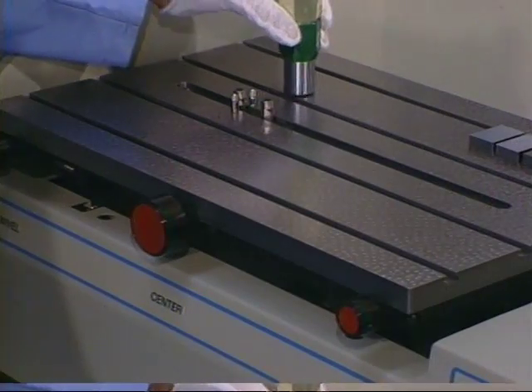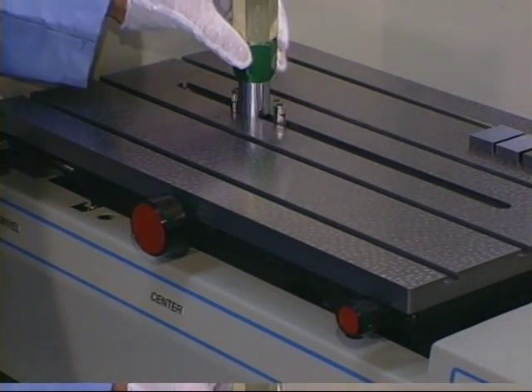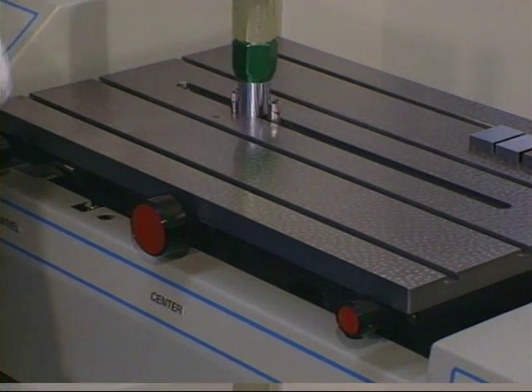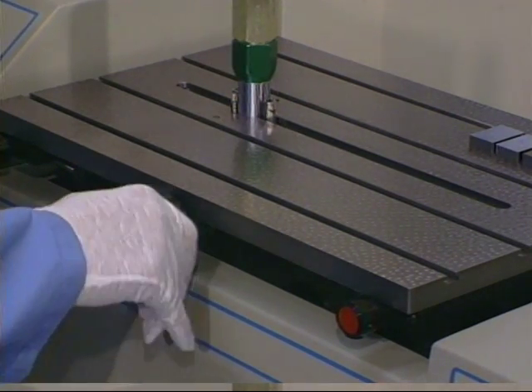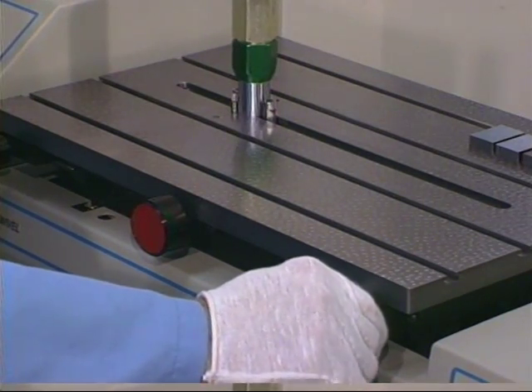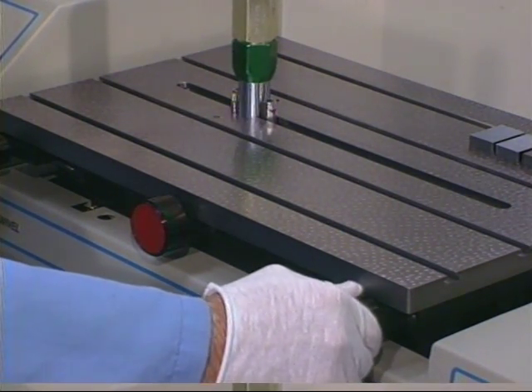Plug measurement is accomplished by placing the plug against the locating post. Close the probes on the gauge. Adjust the center to find the maximum diameter and the tilt to make sure that the face of the plug is perpendicular to the line of measurement.